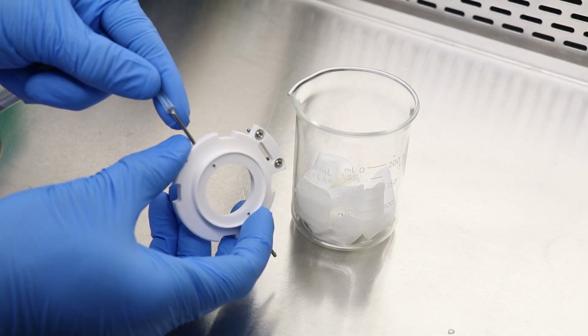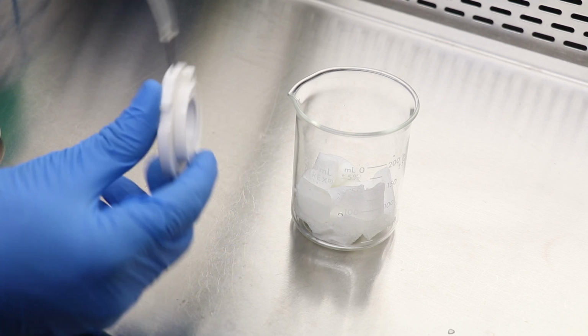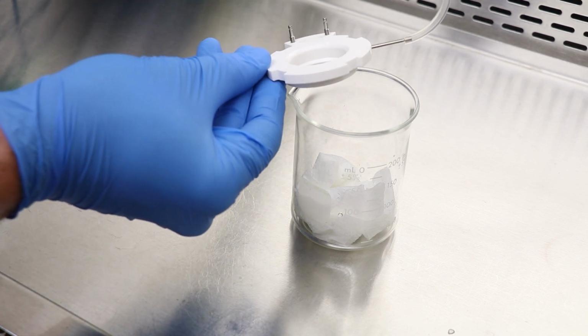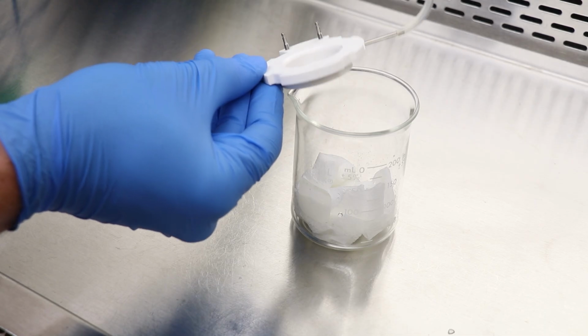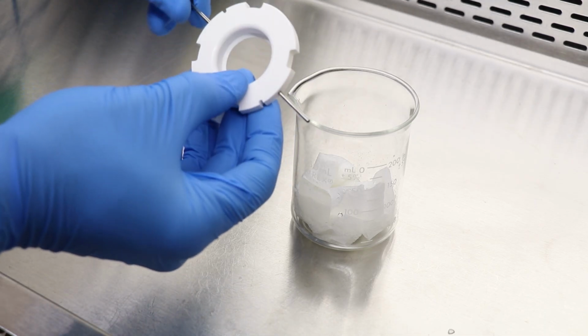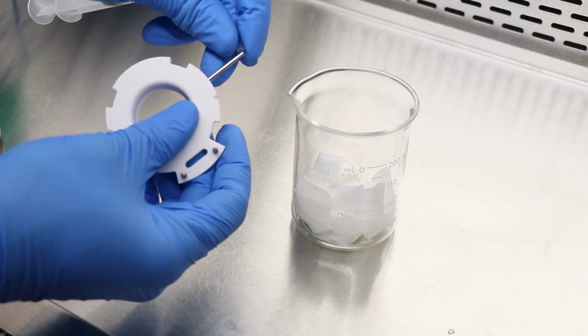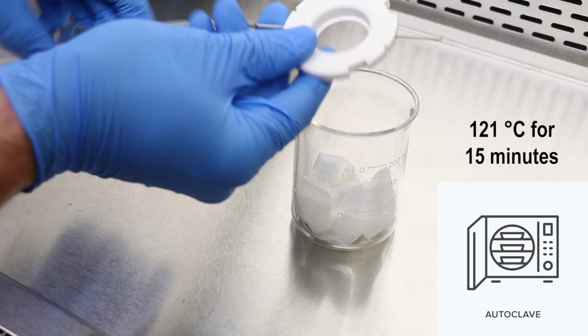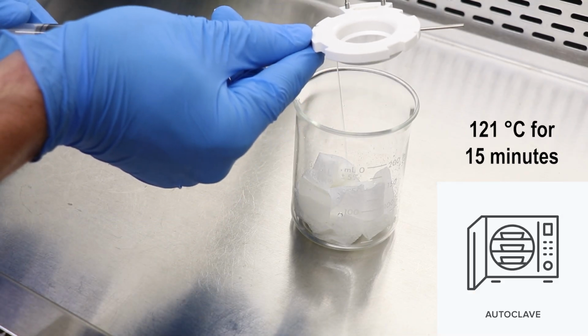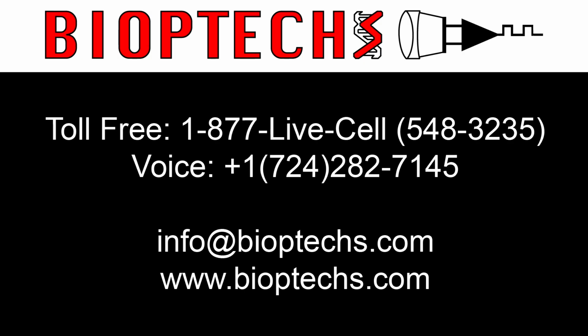Now perform another flow check with distilled or deionized water. If the blockage has been removed, you are now ready to finish with a sterilization step in an autoclave, 121 C for 15 minutes. Then the top can be returned to service. If the resistance cannot be resolved, then it is suggested to return the top to Bioptechs for service or a new top purchased. Please contact a Bioptechs representative.